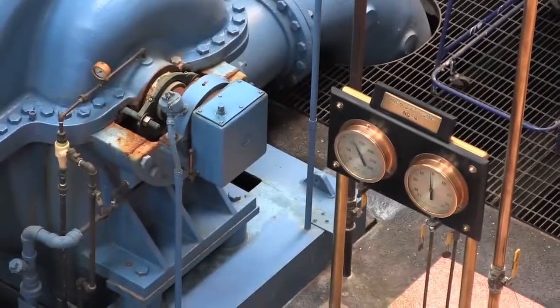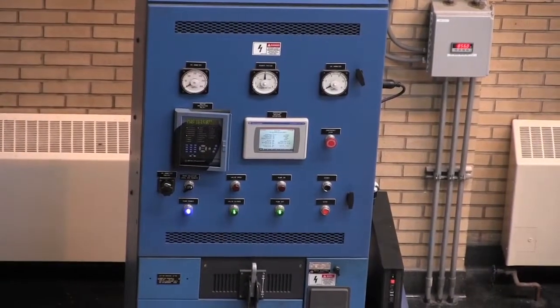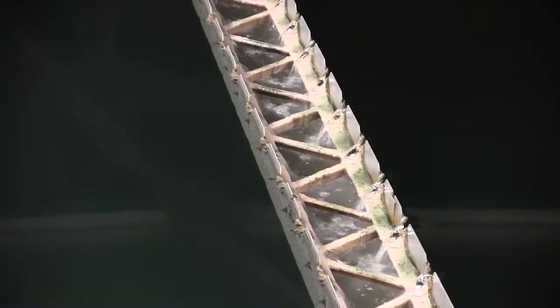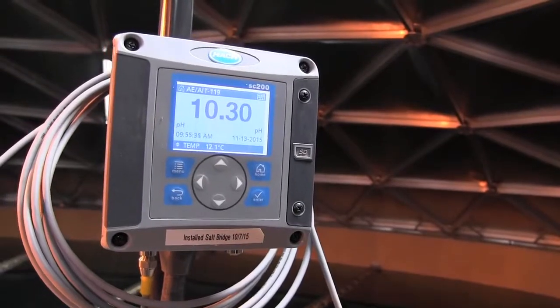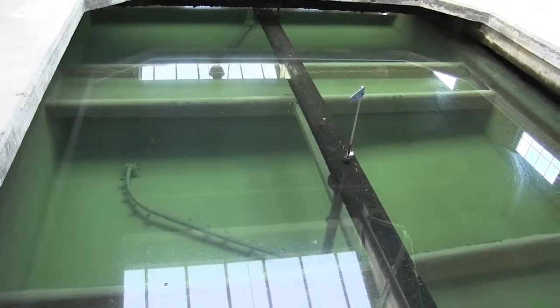The water's screened. It then travels through a long series of pipes, goes over and has coagulant chemical added, goes through our new SCUs, which allows the dirty water to come in through the middle. That's the mixing of the chemicals with the dirt particles. So you have lime, you have something called aluminum chlorohydrate, and then you have dirt. The cleaner water comes through the filter building here.